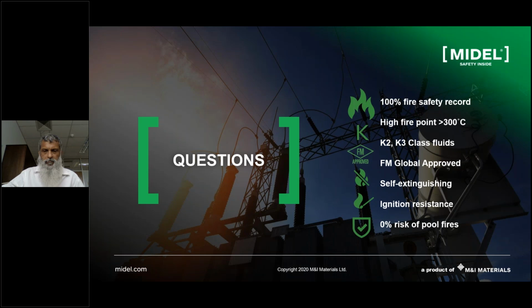A question here from Rob Lloyd. Does the ester, once refilled, have to be taken offline and filtered under temperatures as with mineral oil transformers? So if I understand, the question is if we can treat the liquid in a similar way as mineral oil through filtration. Does it need to be filtered? Yeah, what we need is to first assess the liquid condition. So it's in a similar manner as mineral oil. If you have high moisture content in the ester, we need to filter it, vacuum dry it, and so it can be under the same procedures of filtration as mineral oil, but usually we don't need to, only if the in-service parameters indicate so. Okay.